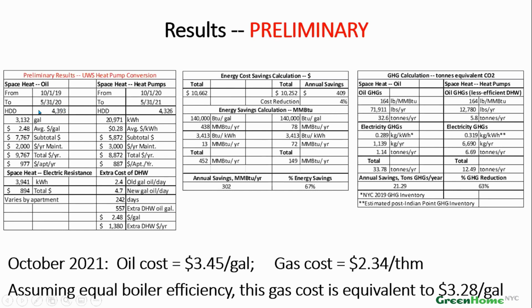What we had in this building is for the winter of 2019-2020, there were about 4,400 degree days. We calculated them to have used 3,100 gallons. Here's the average price, so there's a subtotal of energy cost here, about 7,700. But then we also had to include maintenance costs, and for this building it averaged about 2,000 a year for the last 5 years.